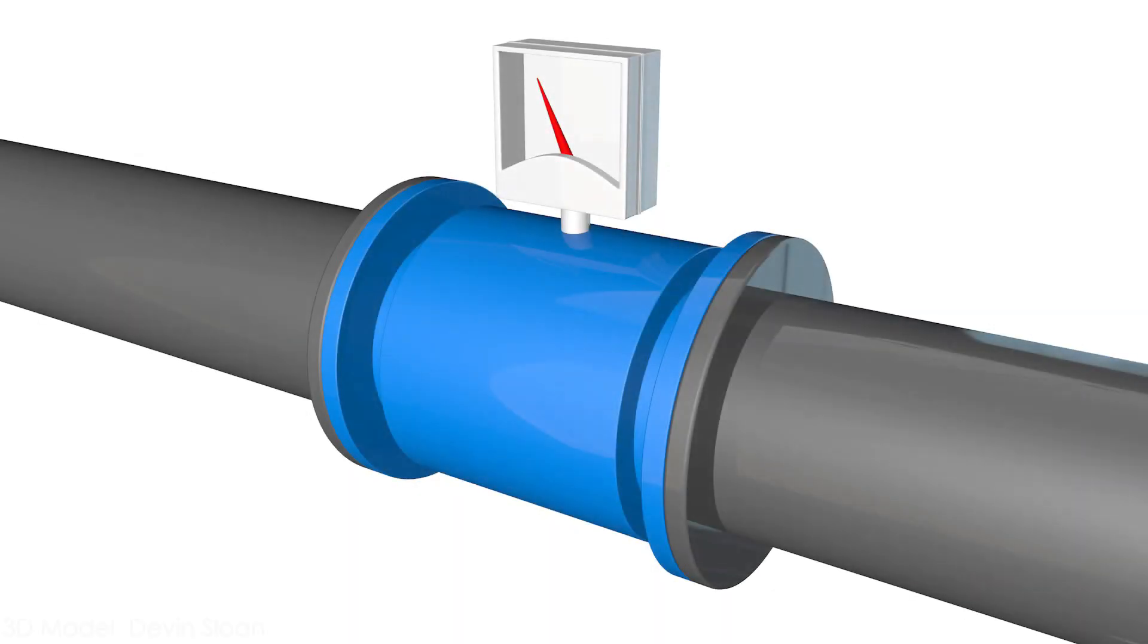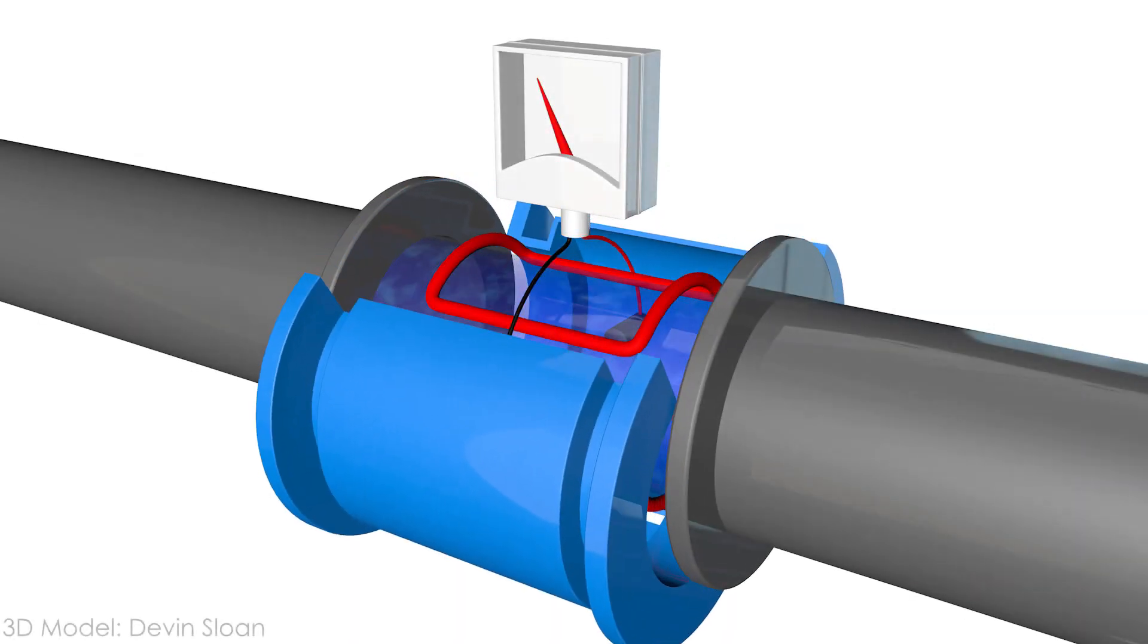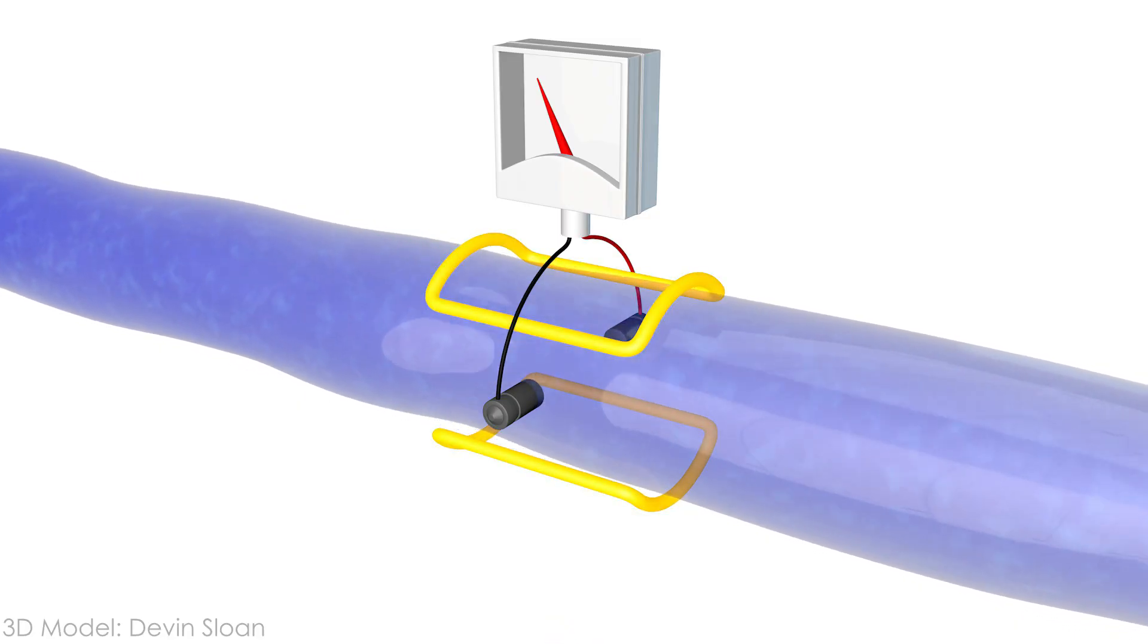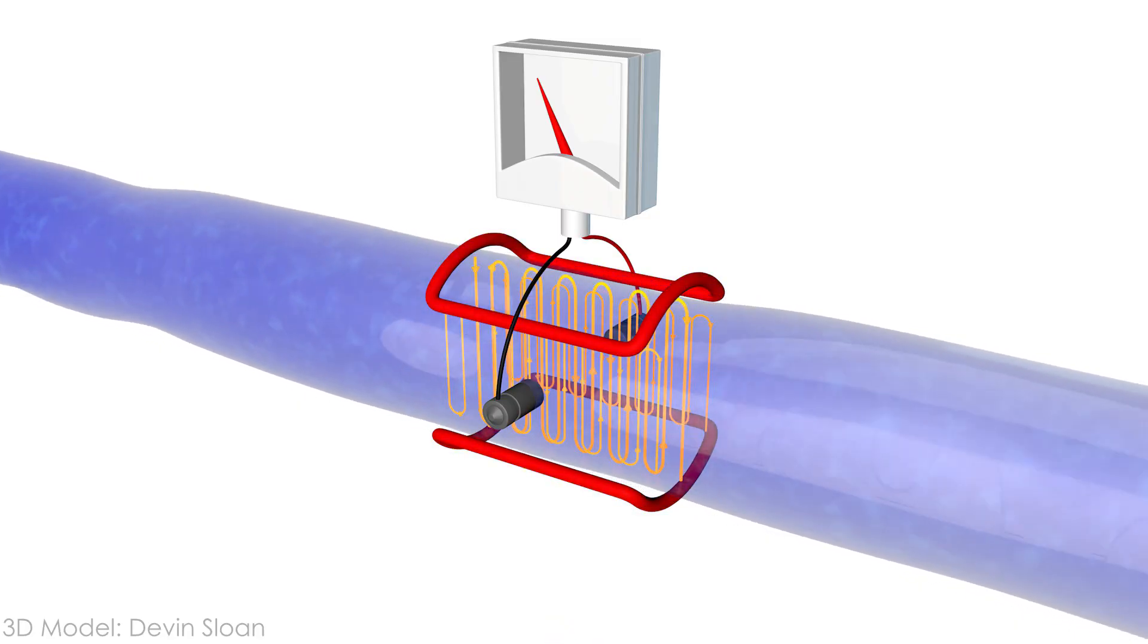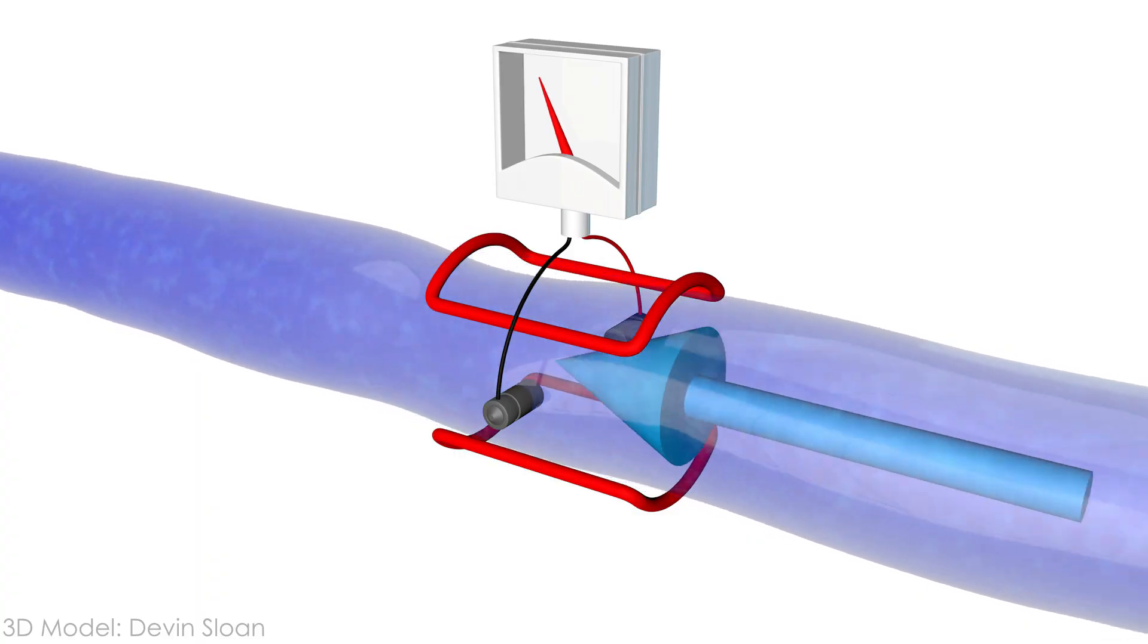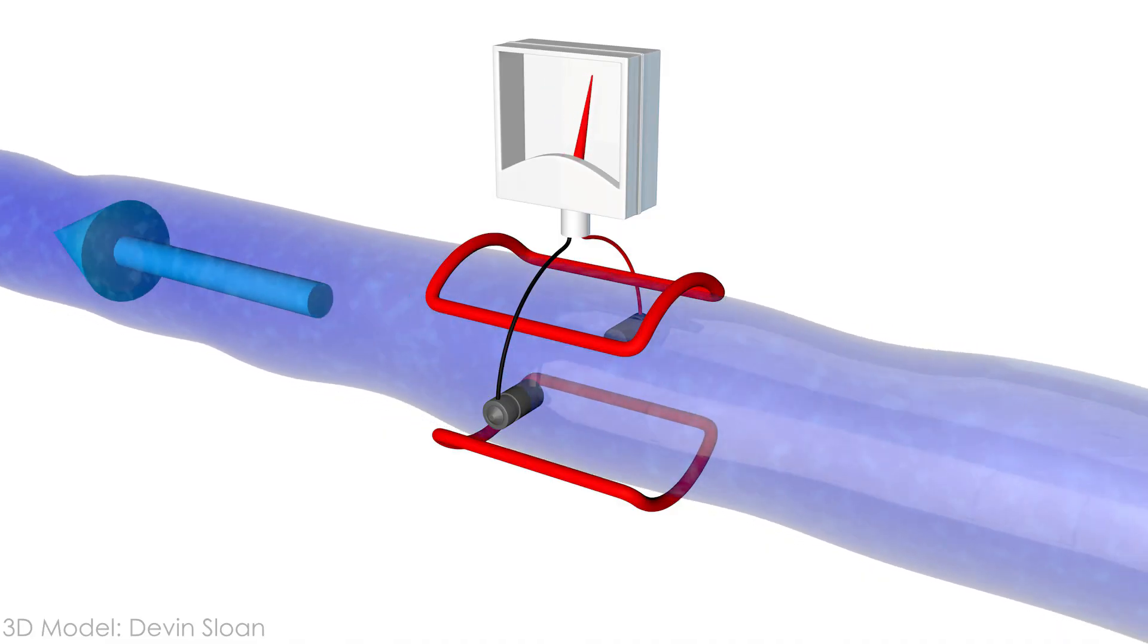A magnetic flow meter works exactly the same way, except instead of wire, the conductor is a fluid in a pipe. Magnets outside the pipe create a magnetic field. Electrodes are located perpendicular to the magnets. A conductive fluid moving through the pipe will generate a voltage between the electrodes due to Faraday's law. The faster the fluid moves through the pipe, the higher the voltage.